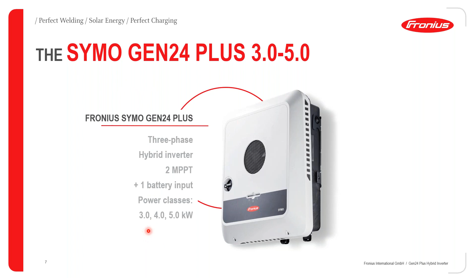And the other variation that is available for the Symo Gen24 Plus are the inverter power classes from 3 to 5.0 kilowatt. So they do also have two MPPTs, one battery input, but they have a slight variation with the power class 6.0 up to 10 kilowatt. So as you can see, the smaller Symo Gen24 Plus inverters are available in 3, 4, and 5 kilowatts. But in terms of the comparison between the smaller power class up to 5 kilowatts and the bigger power class 6 to 10 kilowatts, we can see that we have some slight variations, like in terms of the MPPT connection. We can do up to 12.5 amps on either MPPT on the smaller power classes, but you can do a connection of up to 25 amps for the bigger MPPT, MPPT1, and 12.5 amps for the second MPPT.